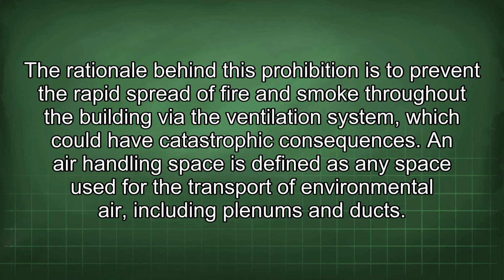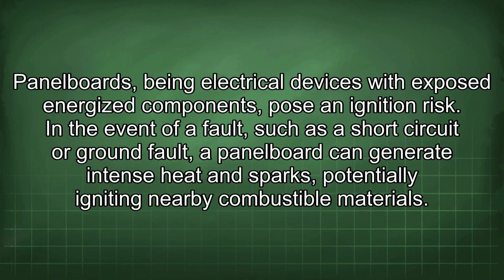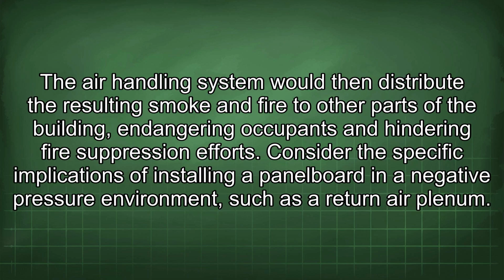An air handling space is defined as any space used for the transport of environmental air, including plenums and ducts. Panelboards, being electrical devices with exposed energized components, pose an ignition risk. In the event of a fault, such as a short circuit or ground fault, a panelboard can generate intense heat and sparks, potentially igniting nearby combustible materials. The air handling system would then distribute the resulting smoke and fire to other parts of the building, endangering occupants and hindering fire suppression efforts.